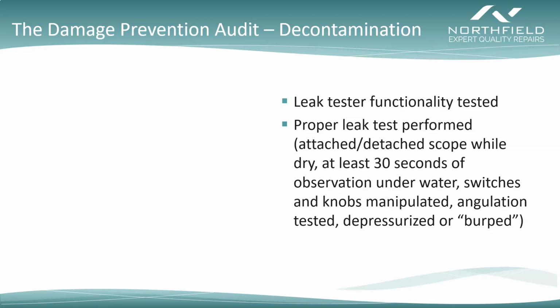Again, the specific instructions for this will be outlined in your manufacturer's IFUs. But generally speaking, we want to see that the leak tester is attached and detached from the scope while dry, not underwater. We want to see at least 30 seconds of observation underwater. We want to see those knobs and those switches being manipulated, turning those angulation knobs. This is another great time to check that angulation system to make sure that it's working properly.